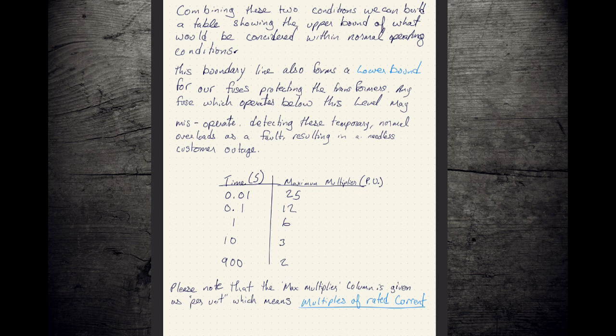By the time we get out to 10 seconds, we see that we've dropped to 30, a multiplier of 3. So our little 10 amp transformer is now only flowing 30 amps, which, if you're comfortable with that, you shouldn't be. You shouldn't be flowing 30 amps through something that says I'm only good for 10. By the time you get out to 900 seconds, 15 minutes out, we still might be seeing 20 amps flowing through our transformer only rated for 10. And then at some point beyond that, we're going to trickle back down to whatever our nominal load was.